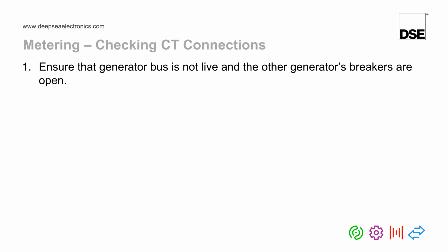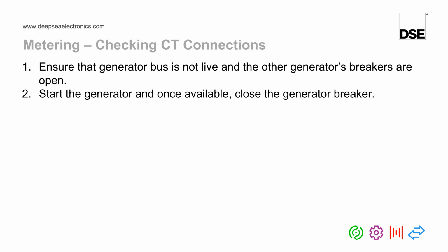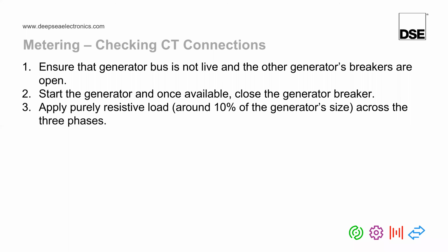So really metering, it's checking that the current transformers are wired correctly to the DeepSea module. So to do this procedure, what we first need to do is make sure that the generator bus is not live and no other generators are connected to it, so their breakers are open. We're then going to start a generator and once available, close the generator onto that bus. And we do then need to apply a purely resistive load around 10% of the generator's size to the bus.